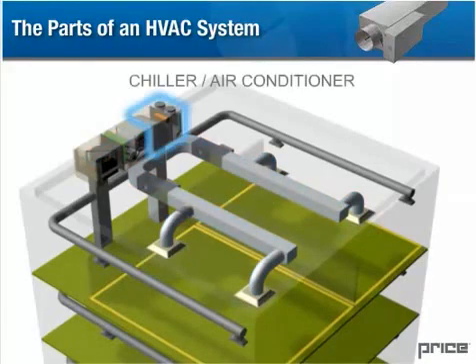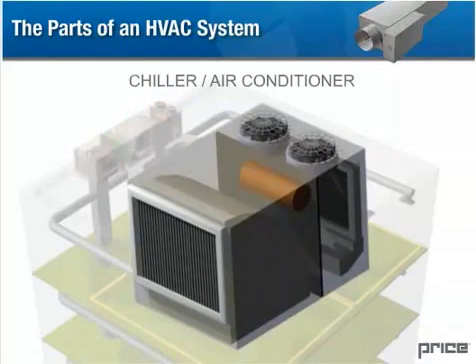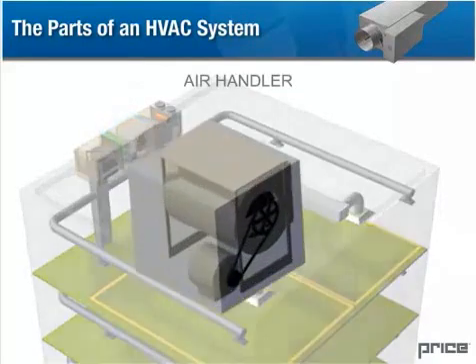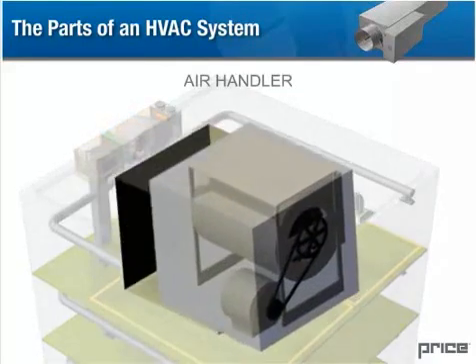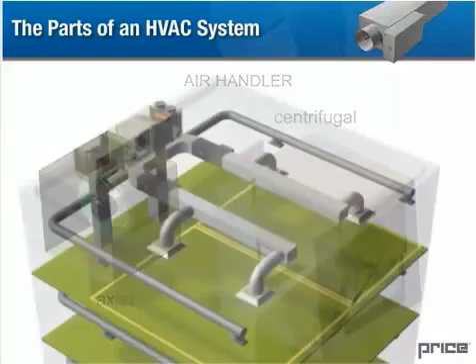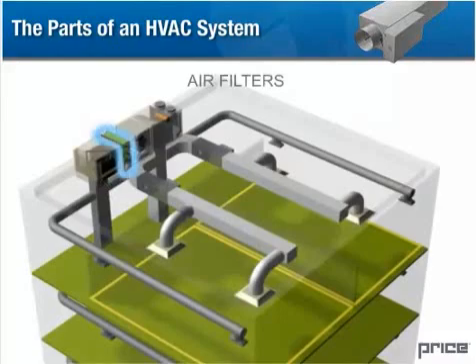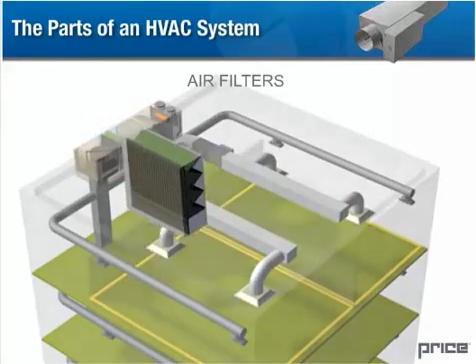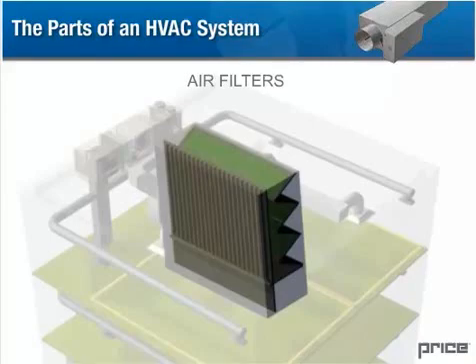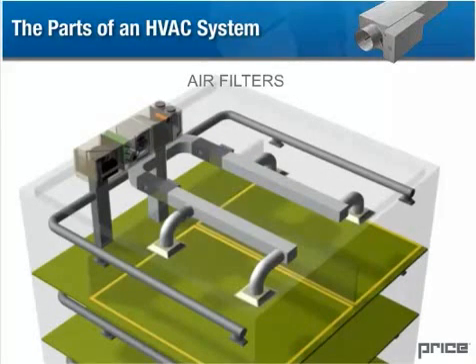The chiller or air conditioner utilizes heat exchangers and circulated fluid or gas to cool the air that is passed through it. The air handler is a fan or a blower that moves air throughout the building's ductwork. Axial or centrifugal fan types may be found in the air handler. Air filters: depending on the requirements of the occupants and the activities in the building, various grades of air filters are used in the system. General purpose air filters will be included in the air handler itself, while more sophisticated filters, such as HEPA filters, may be used in the downstream ductwork.